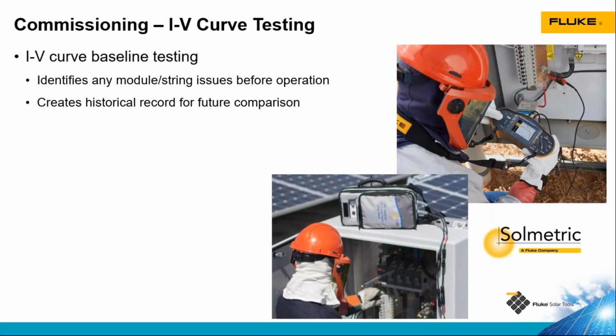During commissioning, we also do IV curve testing. This is a test to ensure that our modules are operating properly. We do this at commissioning to make sure everything's working right when we first start up the system. We're also setting a baseline that we can refer back to in the future if things change over time.